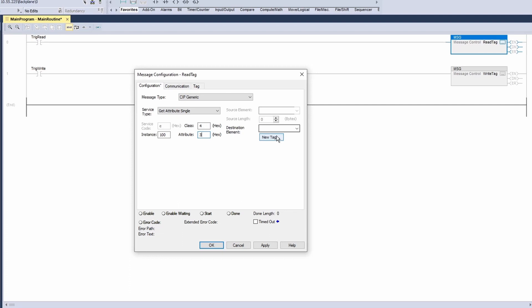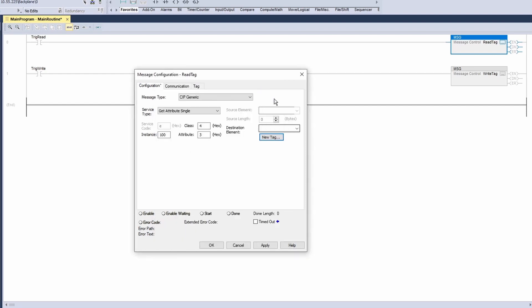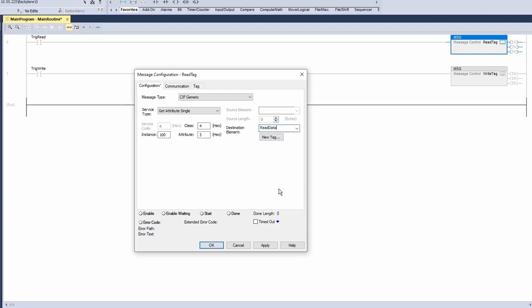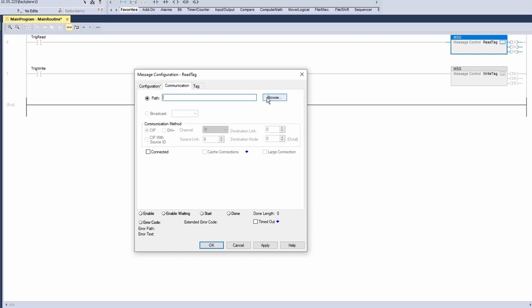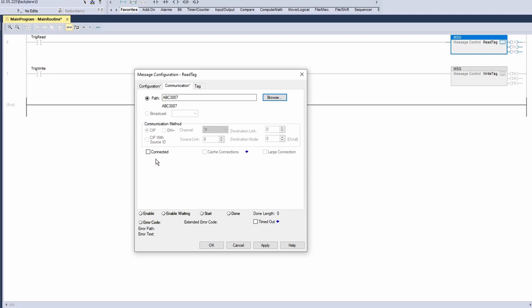Click new tag, name it read data, and set the data type to an array of 6. Click create. Select the created read data in the destination element. Go to the communication tab, click browse, select the Anybus Communicator, and click OK. Check connected and cache connections. Click OK to finish the read message instruction.